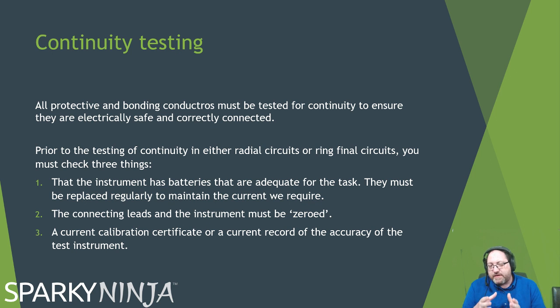The test is called continuity of protective conductor, and what you need to remember is, if I install a circuit and I put something at the end of it and I turn it on, if the thing works, then it's likely that neutral and line have got there and they're doing their job. You don't know if the protective conductor or the earth is actually there, because if the thing has no earth, let's say it's equipment like a shower or something, if the earth hasn't got there, the absence of an earth isn't going to make that stop working. It's just going to carry on working. So you've got no idea.